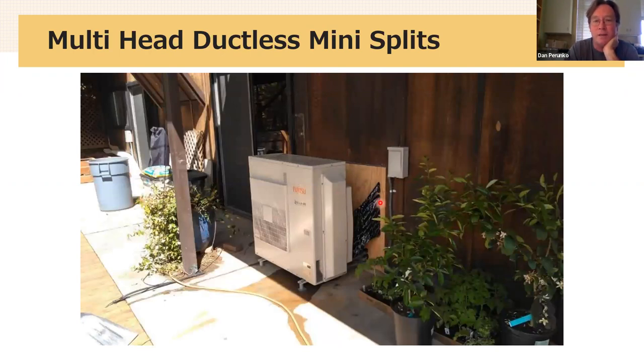Now, this is an installed multi-head. You see how there's eight lines right here? It might be a little hard to count. There are eight lines right there. Those are pairs of copper tubes that run the refrigerant from the outside unit to the inside unit. This house has a downstairs guest suite that has one wall head in it. The master bedroom suite has one wall head in it. The kitchen living room area has one wall head in it. And the office in the house has one ceiling cassette in it.